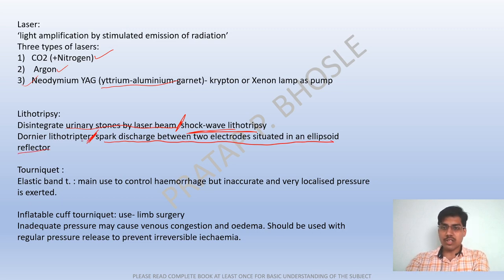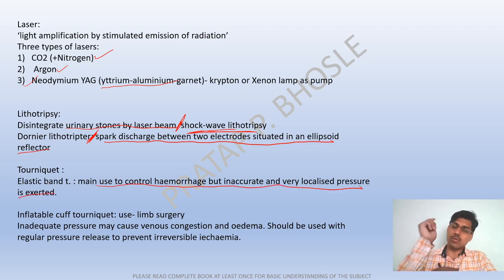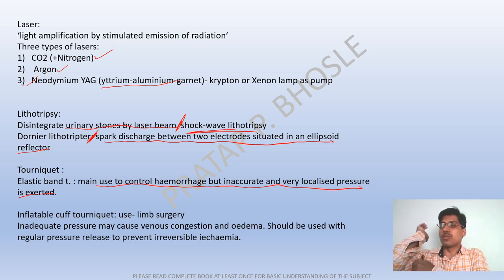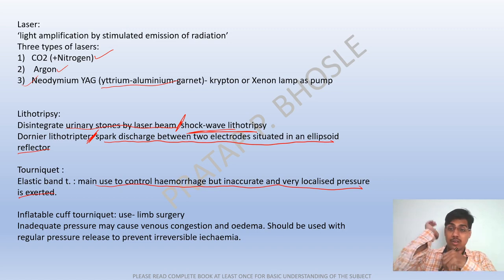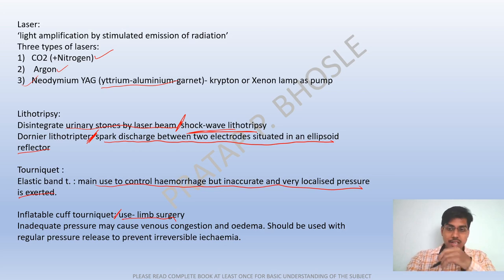Dornier lithotripsy is also called spark discharge lithotripsy — it involves spark discharge between two electrodes situated in an ellipsoid reflector. A tourniquet is an elastic band mainly used to control hemorrhage, but it exerts inaccurate, very localized pressure. The inflatable cuff tourniquet is used in limb surgery; inadequate pressure may cause venous congestion and edema.